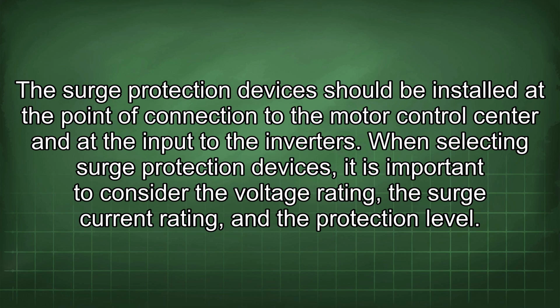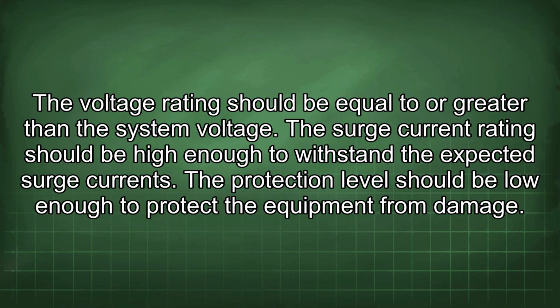The surge protection devices should be installed at the point of connection to the motor control center and at the input to the inverters. When selecting surge protection devices, it is important to consider the voltage rating, the surge current rating, and the protection level. The voltage rating should be equal to or greater than the system voltage. The surge current rating should be high enough to withstand the expected surge currents. The protection level should be low enough to protect the equipment from damage.